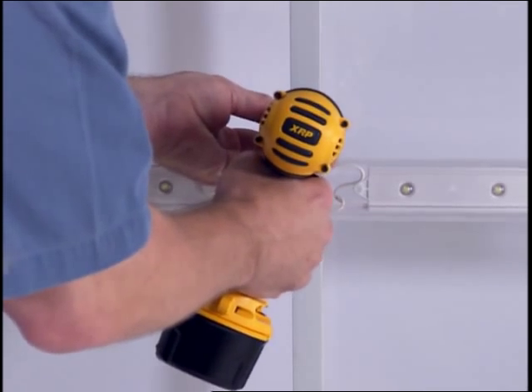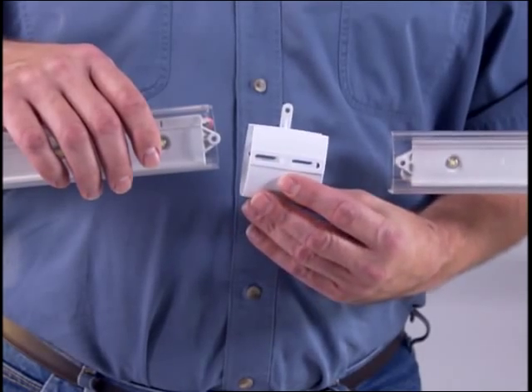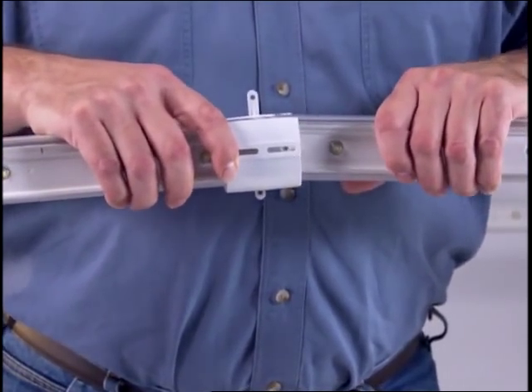For any horizontal assembly greater than four feet in length, you must install support stringers and use assembly supports every four feet. For longer spans up to ten feet, you can install a tube connector on a support stringer. Then, push the tube ends into the connector.